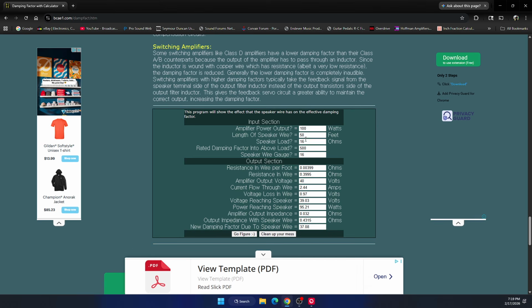Okay, so now let's do the same thing. We're going to go with a 1 foot wire, and we're going to go to 12 gauge. You probably already saw that number before, but we only lost maybe 45 DF. And again, we still have 99.9 watts out of our 100 going there. So you can see the importance now of keeping a short cable with as high a gauge as you practically can.